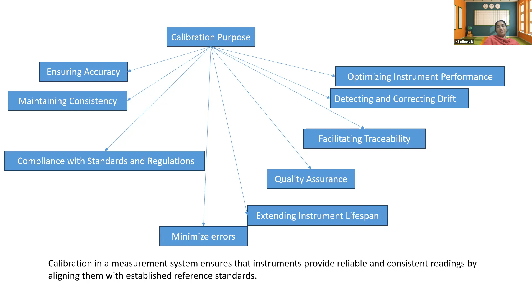So here, let us consider one voltmeter. After doing the calibration process at regular intervals, it reduces the drift inside the voltmeter. What do you mean by zero drift generally? A small value will be indicated even when no input is applied, and that is called the drift. This type of problem can be reduced by doing the calibration. Sometimes bias, offset or linearity issues will come into the picture. Due to this, while doing the measurement, the readings deviate from the true value. Therefore, a static error occurs in the measurement process.